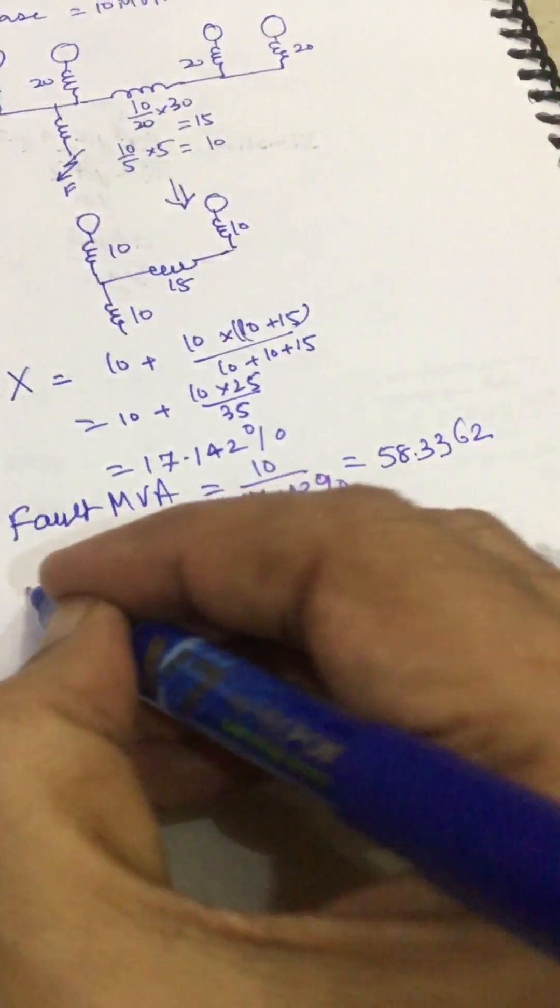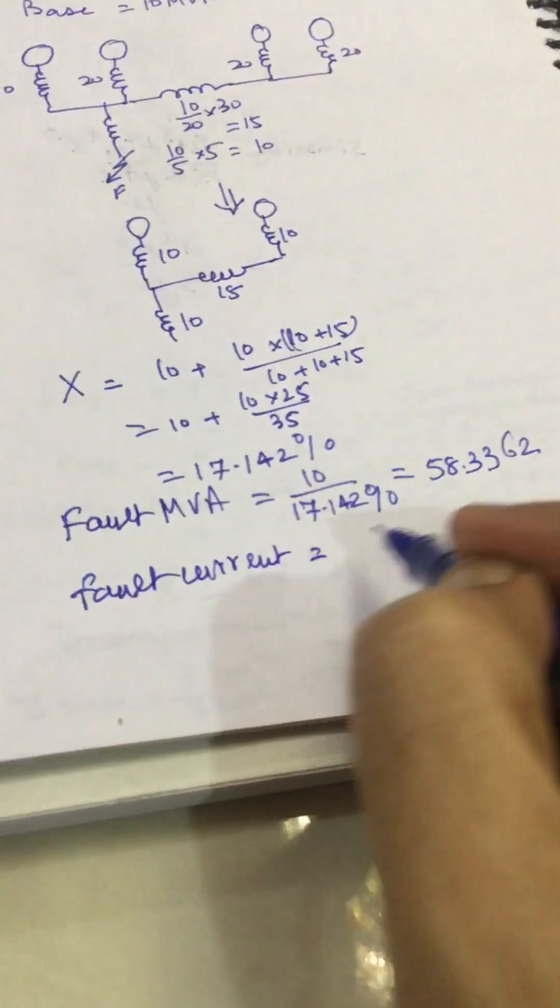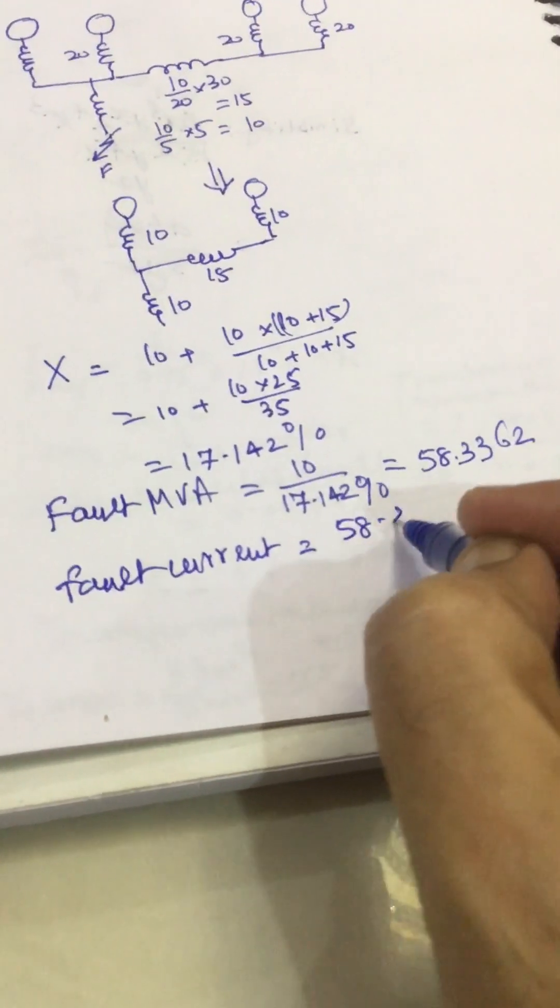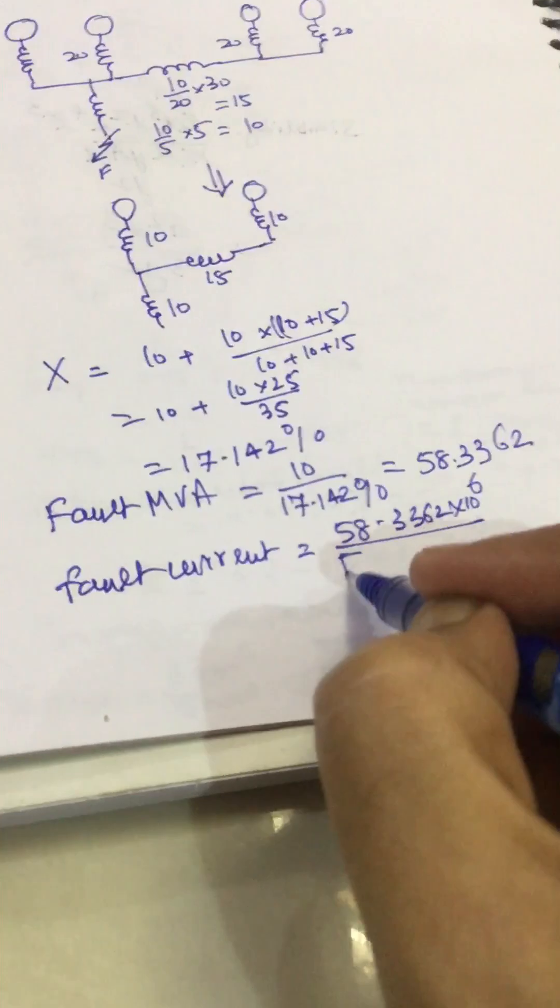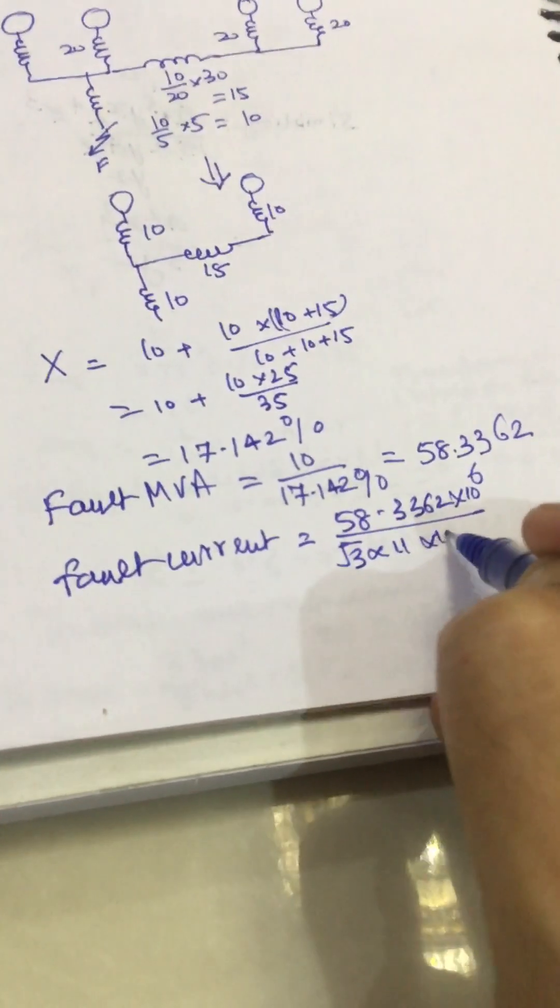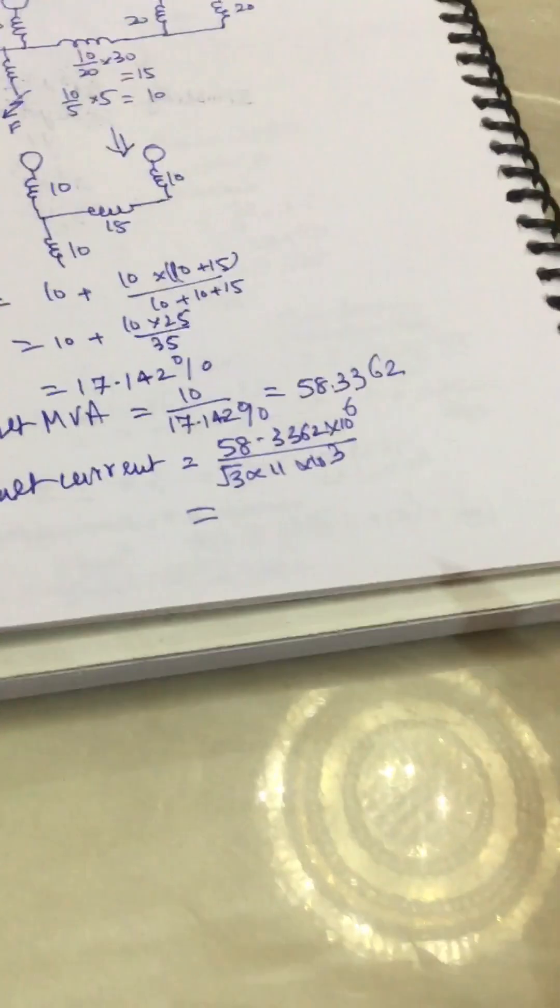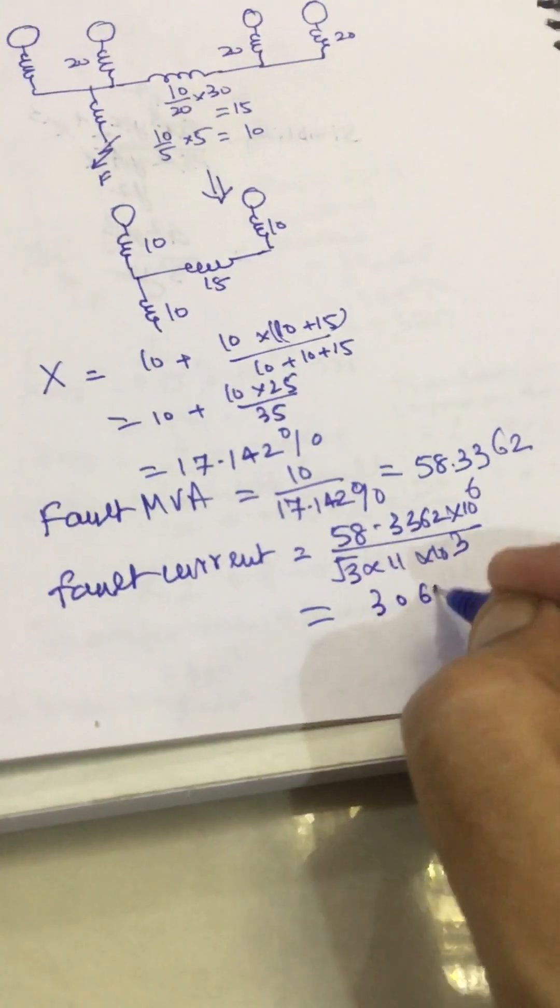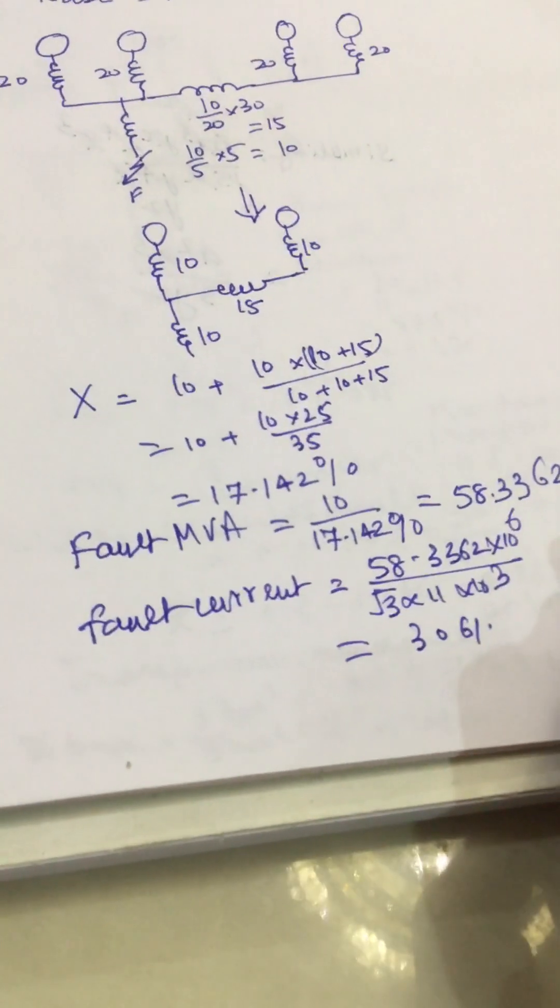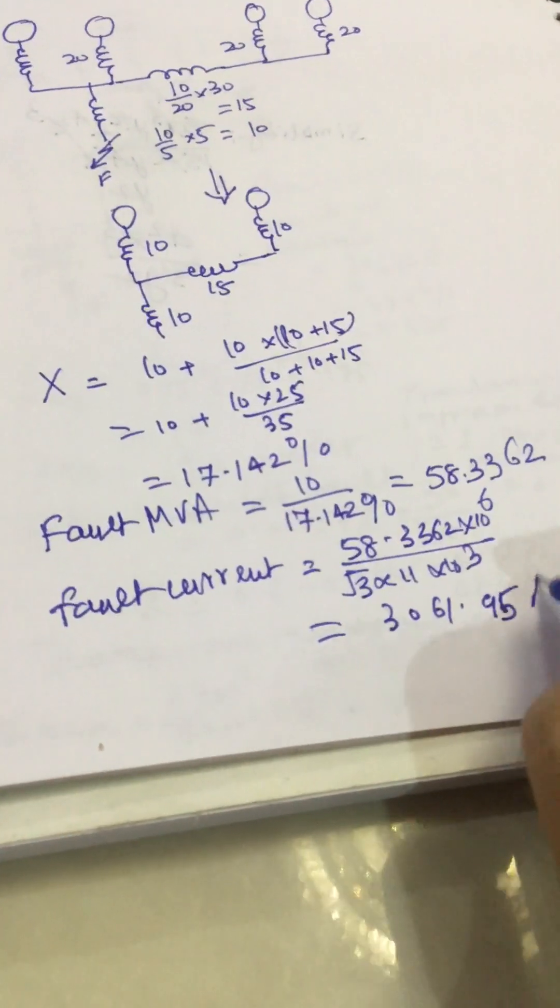Fault current will be equal to 58.3362 multiplied by 10 to power 6 divided by root 3 into 11 into 10 to the power 3 because the voltage is 11 KV. Solving this we get the fault current as 3061.95.